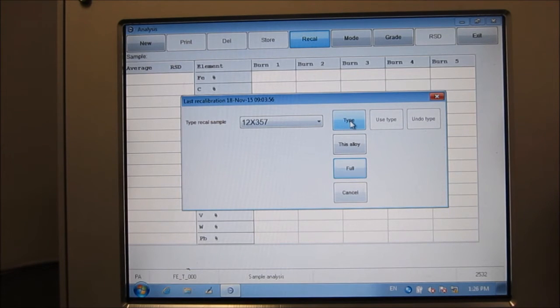For instance, let's say you are having a sample of a stainless steel 316 and you did not get the right value for nickel when you measure it with a known standard. So with type recalibration, you can actually change the curve of the particular element, that is nickel. You can correct this curve of nickel to give you the right reading. This is actually correcting the accuracy of that particular element.